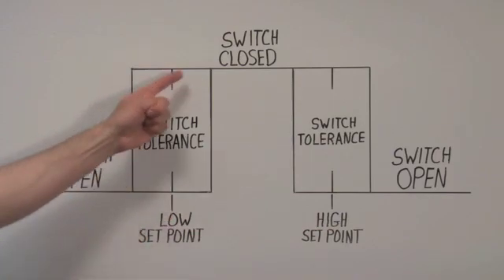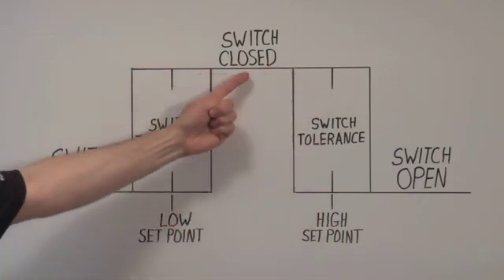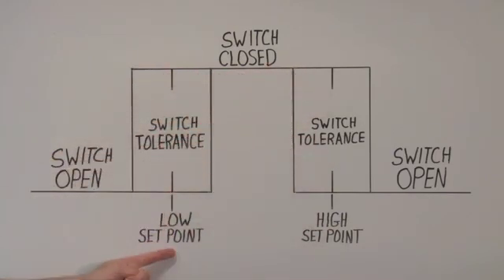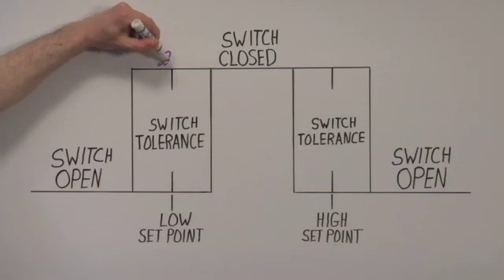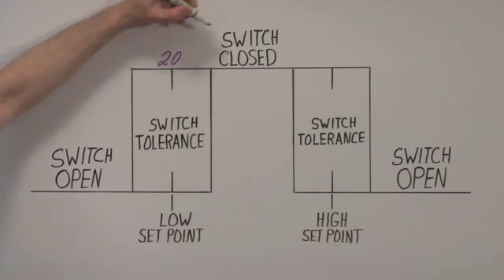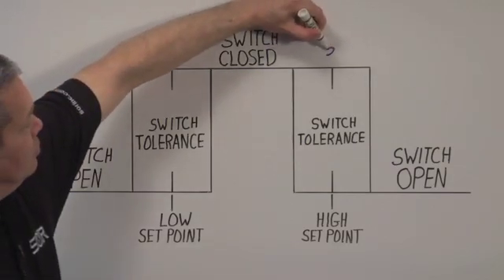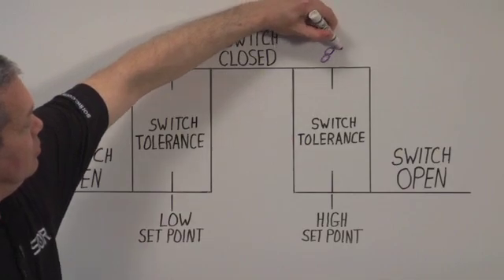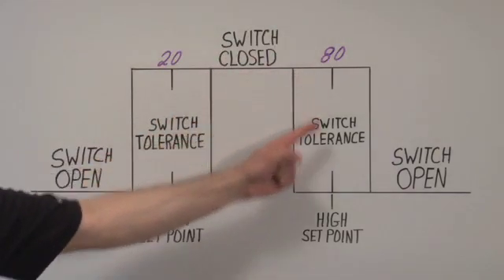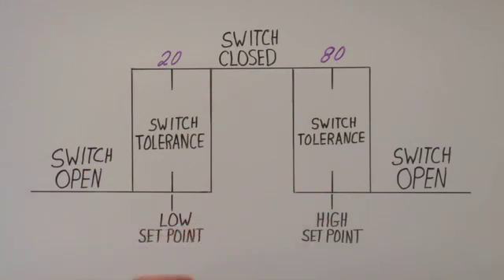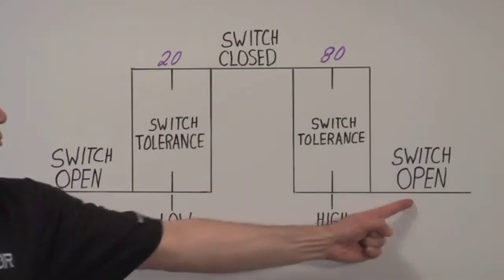On the other hand, the switch is on or closed when the process pressure varies between the low and high set points. This window could be set for an acceptable operating range of 20 PSI to 80 PSI. In this case, the switch will be closed when the pressure being monitored is between 20 and 80 PSI. If the pressure goes below 20 PSI or above 80 PSI, the switch will open.